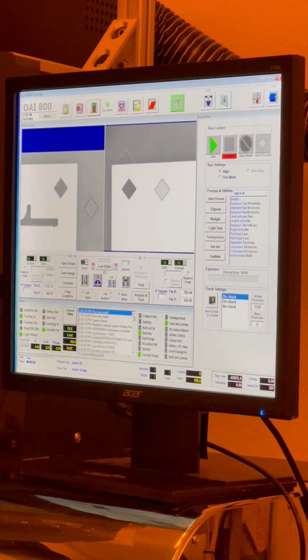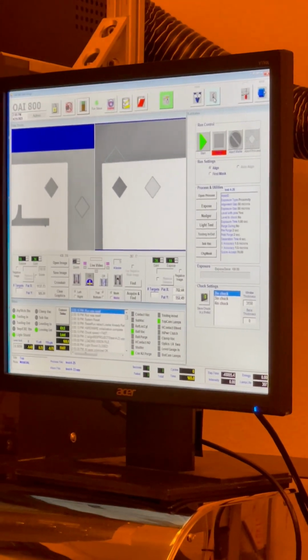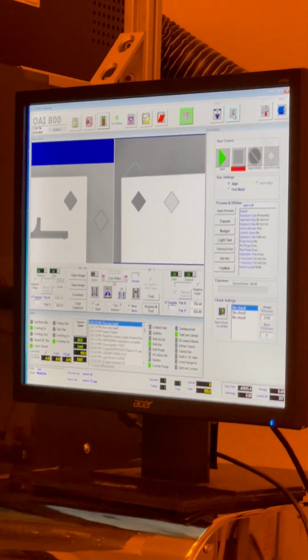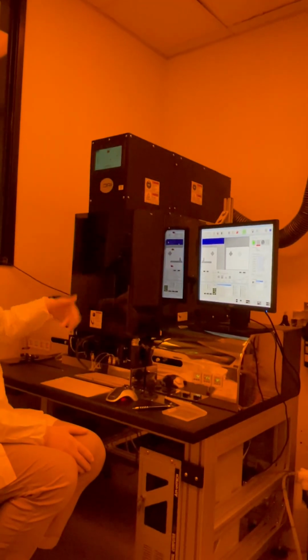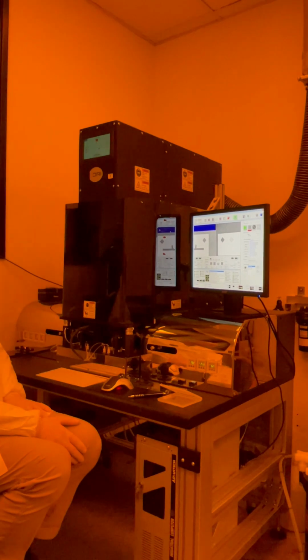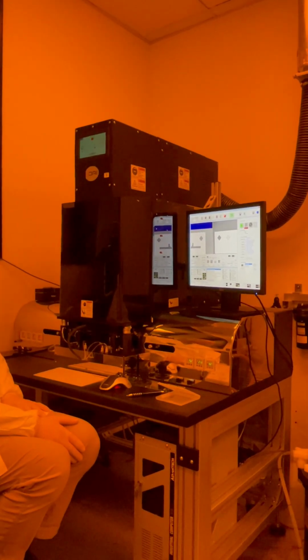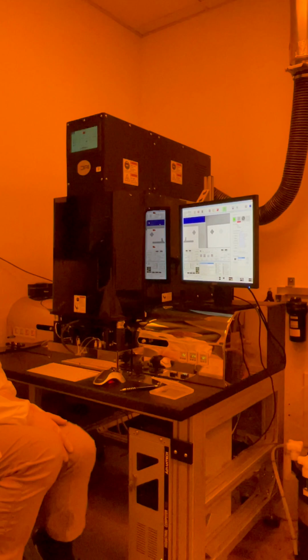Intensity checks. So to do an intensity check, you take your meter, you open the light shield and stick it in there, close the light shield. Everything's through. Turn it on like that. Yeah, and I'll show you how to do that.